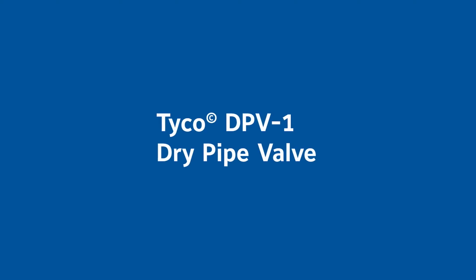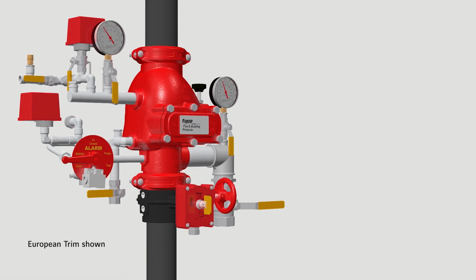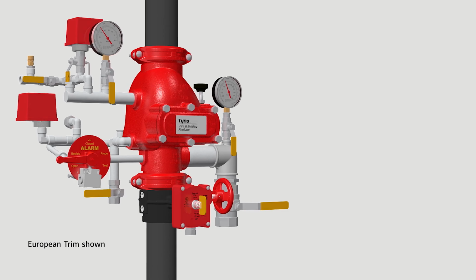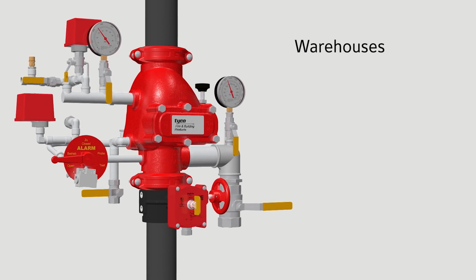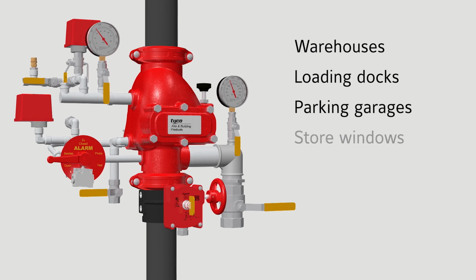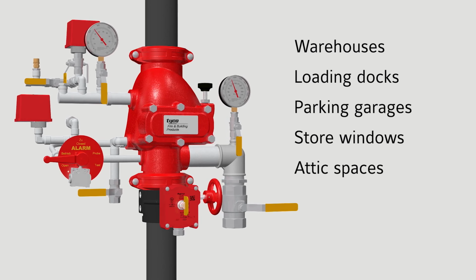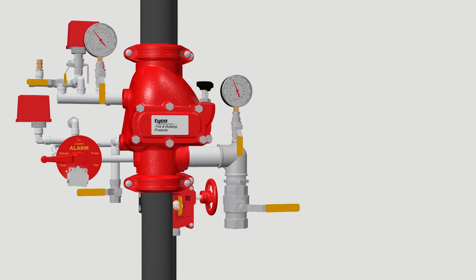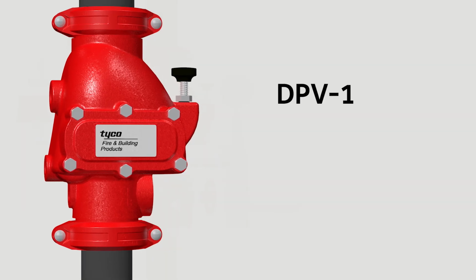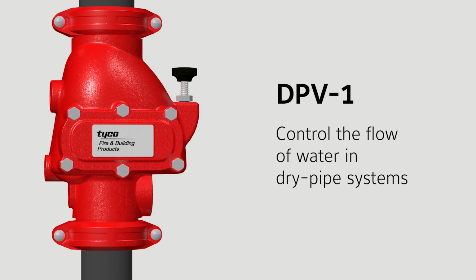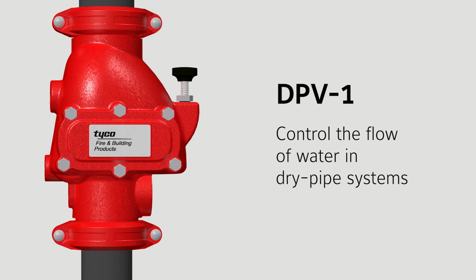The Tyco DPV1 dry pipe valve is designed to protect areas exposed to freezing temperatures, such as unheated warehouses, loading docks, parking garages, store windows, and attic spaces where a water-filled system cannot be utilized. The DPV1 is a differential valve engineered to automatically control the flow of water into dry pipe fire protection sprinkler systems upon operation of one or more automatic sprinklers. The unique offset clapper design is the heart of the system.